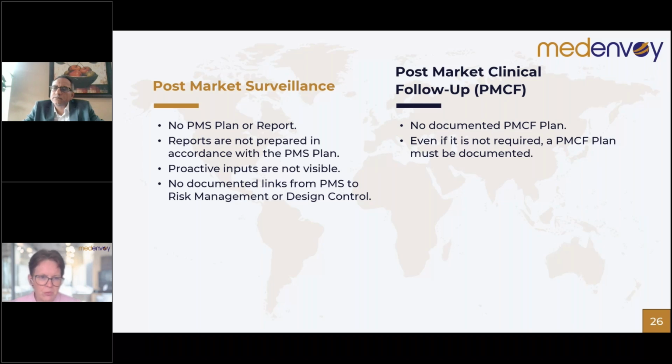And more recently, Swissmedic published their findings from rather large market surveillance activities regarding 30 legacy devices which were high risk, so where even notified body oversight was in place. But then when they reviewed the PMS procedures, the PMS plan, and the PSUR for the devices involved, they identified non-conformities in 20 of the 30 devices that they sampled, which was quite substantial.